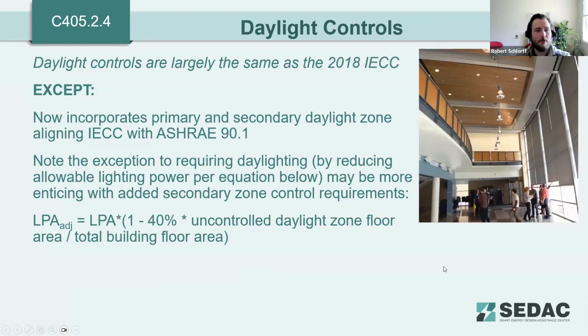Daylight controls. So daylight controls are largely the same as 2018 IECC, except that the 2021 code now incorporates primary and secondary daylight zones, which again is another alignment with ASHRAE 90.1. The exception to requiring daylighting by reducing allowable lighting power per the equation below may be more enticing with this addition of secondary daylight zone control requirements. So keep that in mind, that you may be able to take advantage of that exception with the addition of these secondary daylight zones.